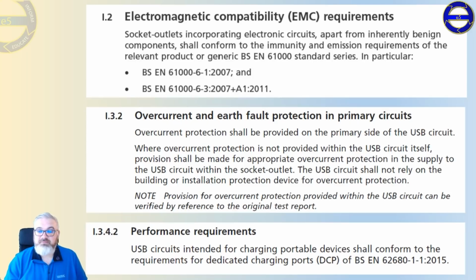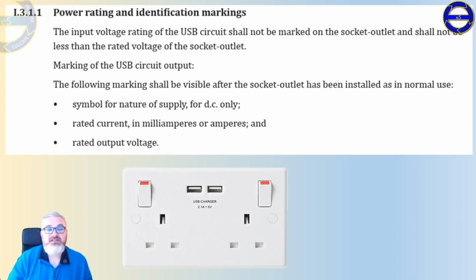You can see why they're cheap. So the last part of BS 1363-2 that is of relevance to the inspector or electrician and installer is in Annex I, which deals with the USB parts. Now, 3.1.1 is about power rating and identification markings, and it states the input voltage rating of the USB circuit shall not be marked on the socket outlet and shall not be less than the rated voltage of the socket outlet, which basically means I don't have to put 240 volt on the front, I don't really have to put it on the back. However, a lot of manufacturers will by default emboss it into the back of the devices.